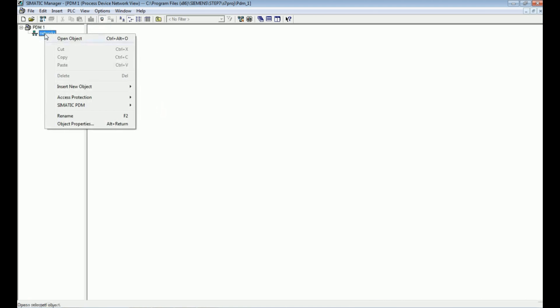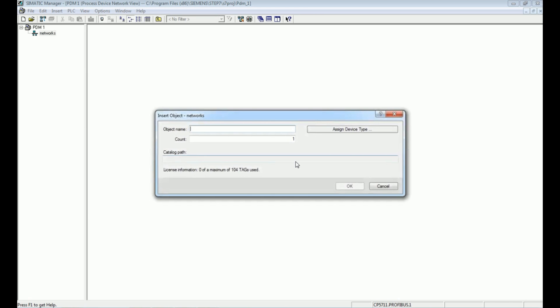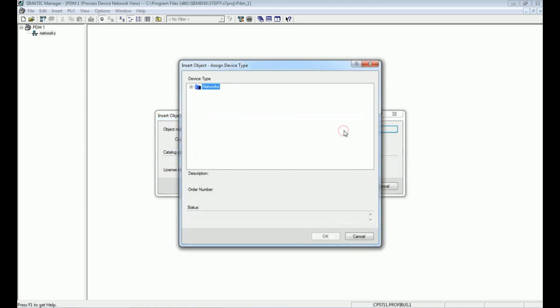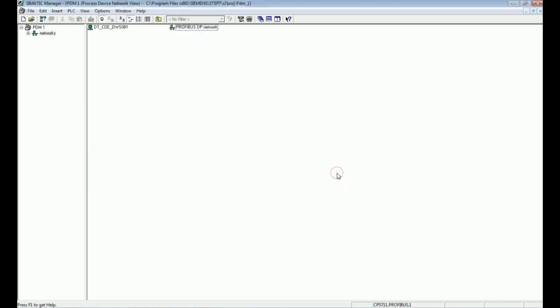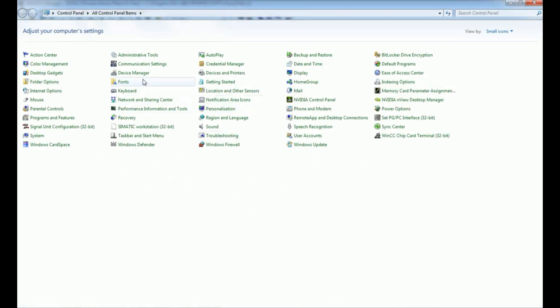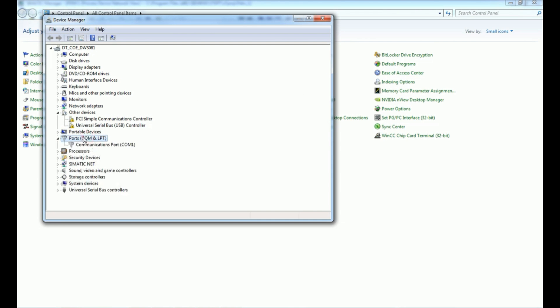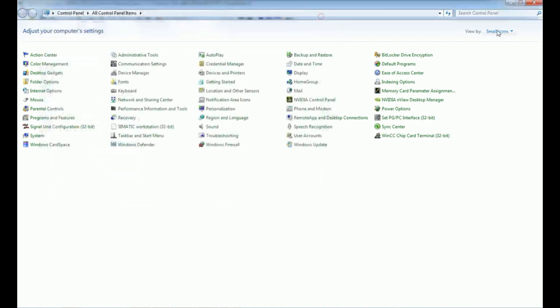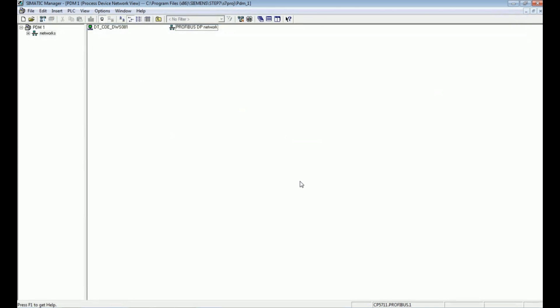Right-click, select 'Insert New Object', then 'Communication Network'. Add the Profibus DP communication network and go to 'Assign Device Type', then press OK. We also need to check the communication port — the communication processor is connected via USB, and we can verify which port it uses from the Control Panel. Open Device Manager and check under Ports — the CP card is connected as COM1. We need to note this communication port when selecting the device.